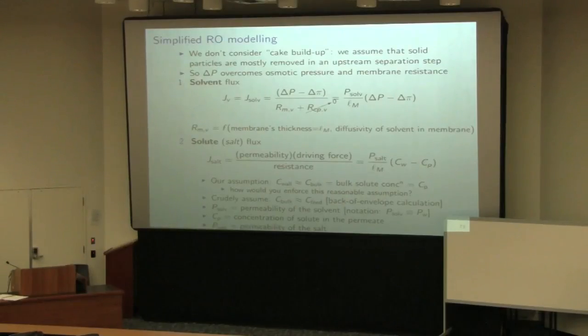But there are some other clever ways of doing that, depending on the nature of the solutes you're working with. By adjusting the pH, you can encourage that solute to remain in solution rather than precipitate out at the membrane surface. That's one approach. Some solutes are also prone to oxidizing reactions and forming salts, so you avoid membrane entrapment prior to feeding that solute into the membrane, which will avoid the solute oxidizing and forming a cake at the membrane surface. There are a number of ways to do that, as well as just keeping the fluid moving very fast past the membrane surface to prevent any buildup there.